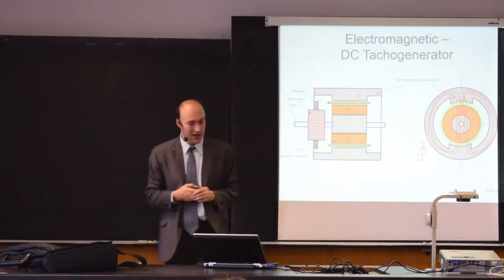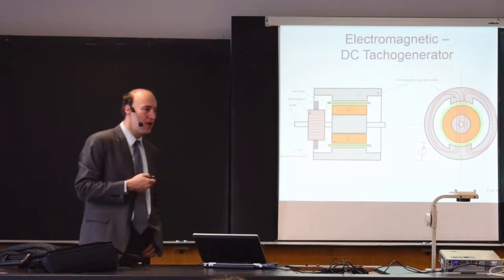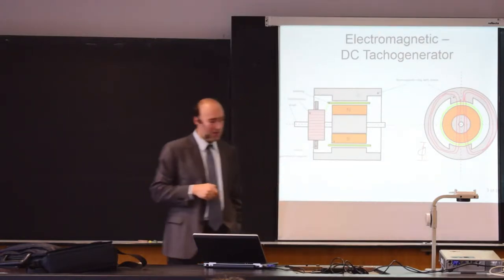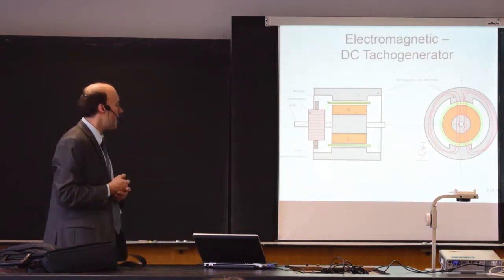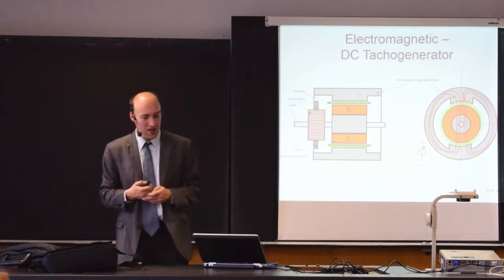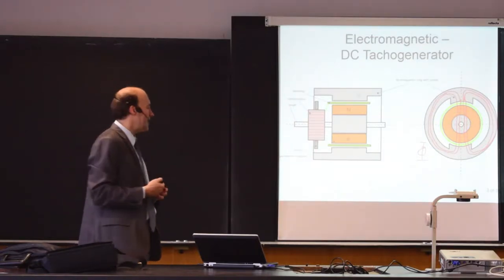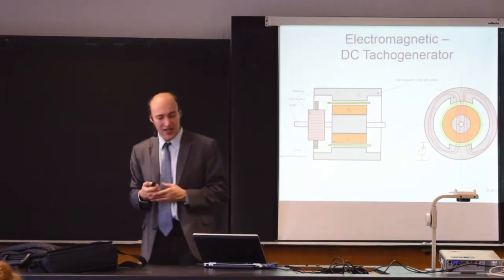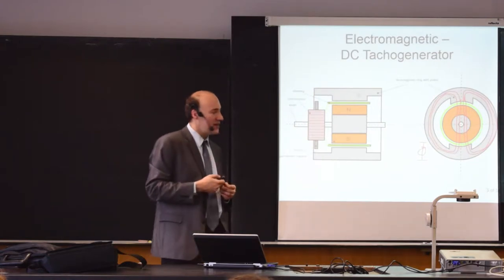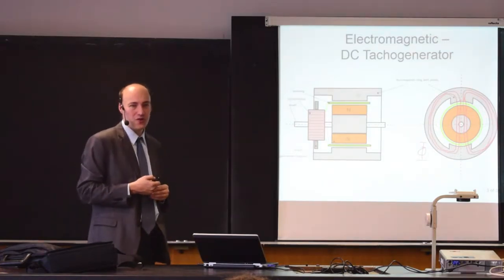The ferromagnetic material is there because we want good conduction of the magnetic flux lines, so we use iron. The air gap needs to be as small as possible because the smaller the air gap, the smaller the magnetic resistance and the better the properties of the machine. But if you make a really small air gap, you may have problems manufacturing the device, so it's a trade-off. The typical air gap is up to about one millimeter — very small, but still possible to produce without extra cost.